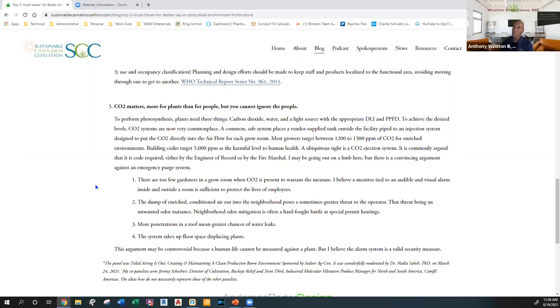That's a good point, and I agree with that point. My thought is the much more dangerous level, right? When it starts getting over human safe levels, where it's harmful at the 5,000 ppm, then I will argue that we need to exhaust all the air. But I think you're correct with the visual and audible. If you set a set point below that 5,000 that says, hey, get out of the room.